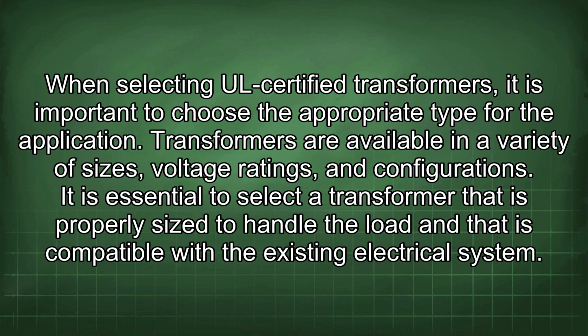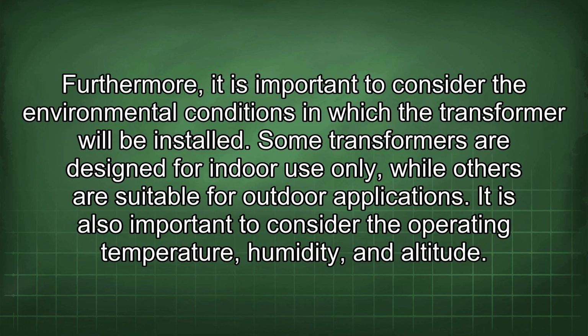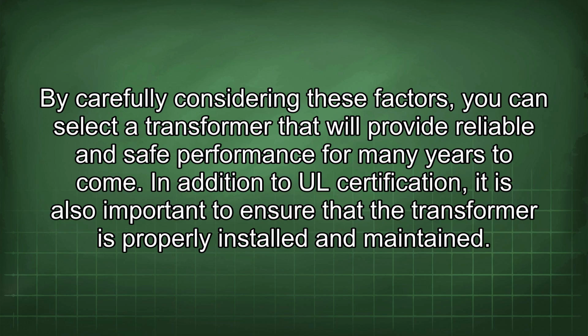When selecting UL certified transformers, it is important to choose the appropriate type for the application. Transformers are available in a variety of sizes, voltage ratings, and configurations. It is essential to select the transformer that is properly sized to handle the load and that is compatible with the existing electrical system. Furthermore, it is important to consider the environmental conditions in which the transformer will be installed. Some transformers are designed for indoor use only, while others are suitable for outdoor applications. It is also important to consider the operating temperature, humidity, and altitude. By carefully considering these factors, you can select a transformer that will provide reliable and safe performance for many years to come.